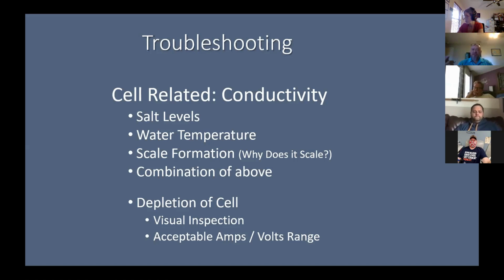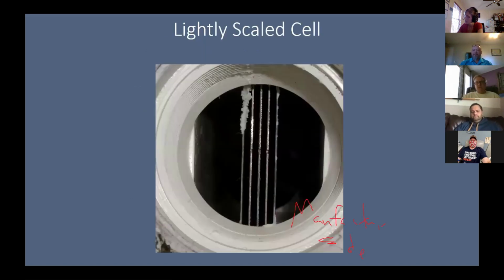One of the other things that you can tell with an autopilot cell, because you can see the edges of the blades inside the cell. Typically on the two outside blades, those are the ones that are receiving the power coming into the cell. So those two outside blades, when the cell starts to wear out, you'll see the leading edge of the blade start to deteriorate, okay? So what's happening is the electrical reaction going through the cell is actually chewing up the edge of the blade, and that coincides with the life of the cell. So as it starts eroding on the ends, the blade itself is making less and less chlorine. All right.